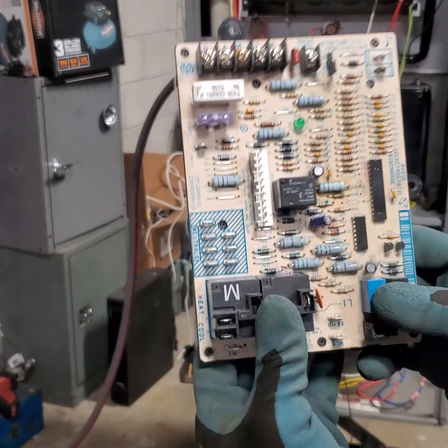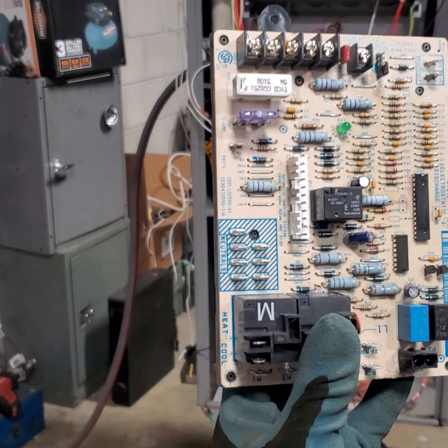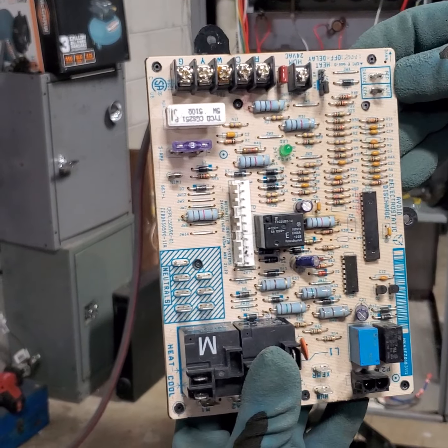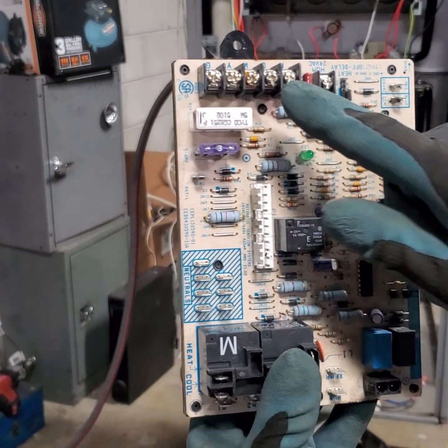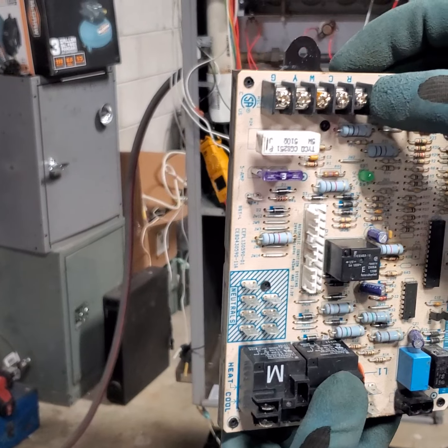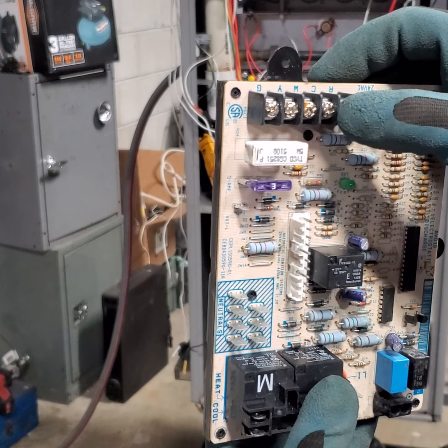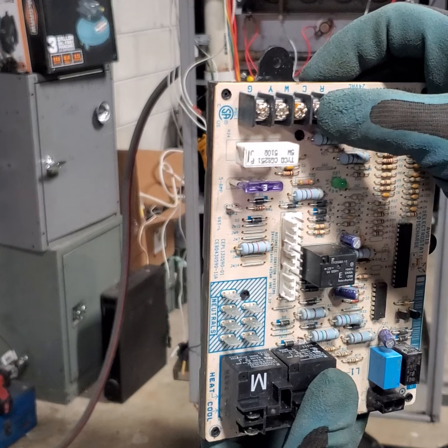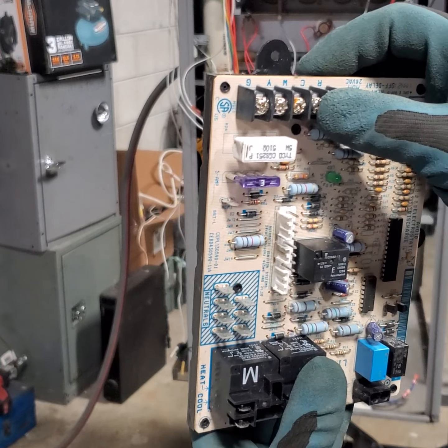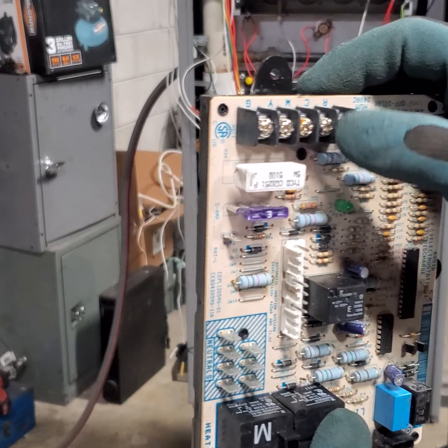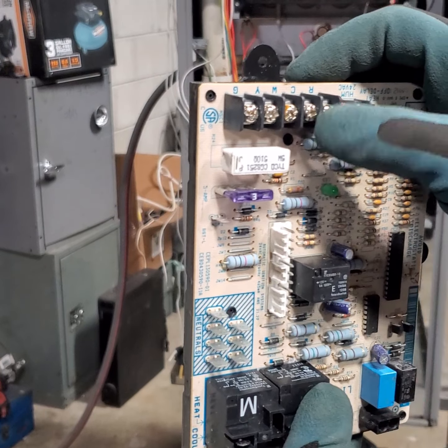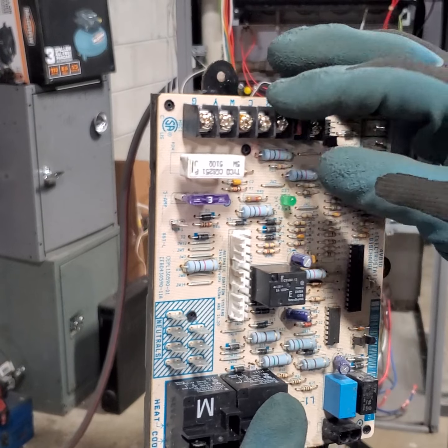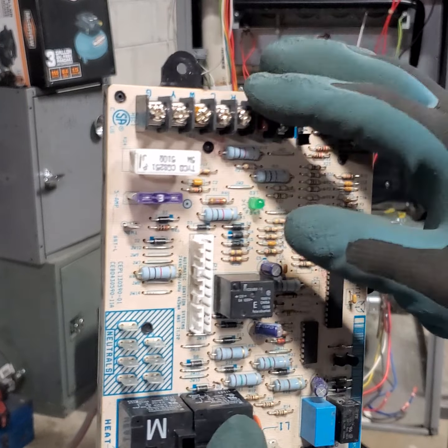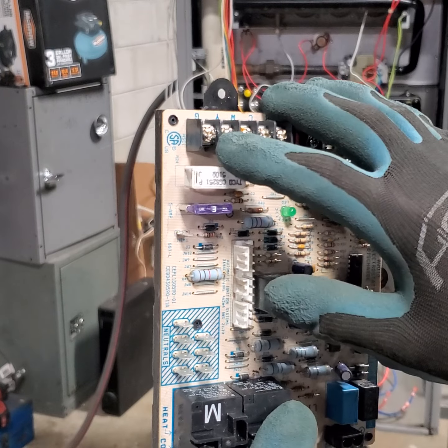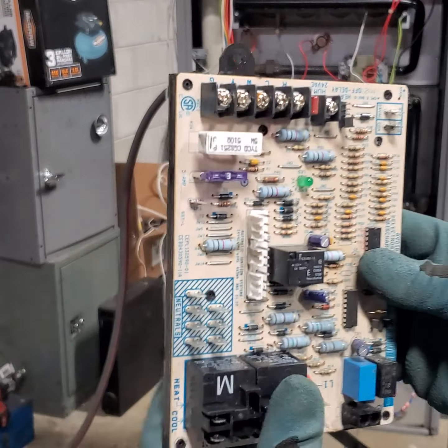So here, as you see: transformer red, blue, thermostat R for R on a thermostat. Common — usually if you want to power a thermostat without a battery, you can use it. If your thermostat has a common, you put a common here from the thermostat, and the thermostat will be powered without a battery. W is for heat, Y is for AC, G is for fan.